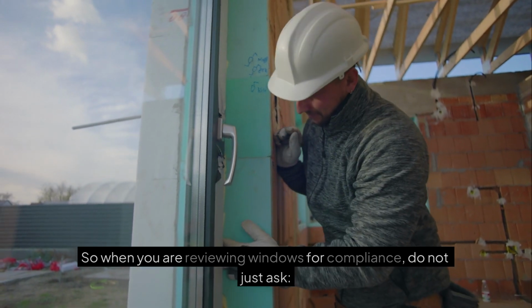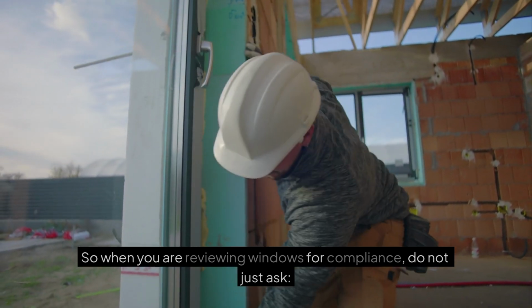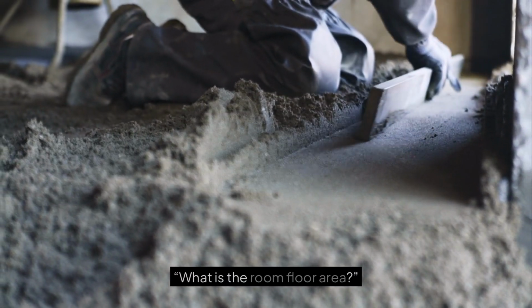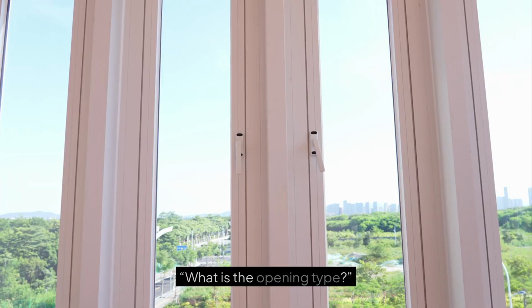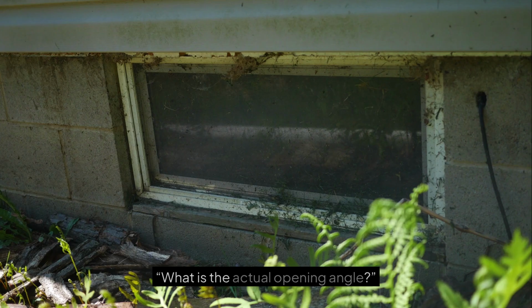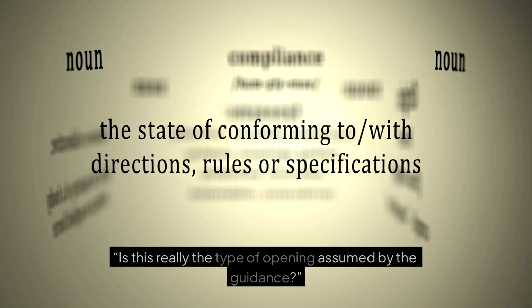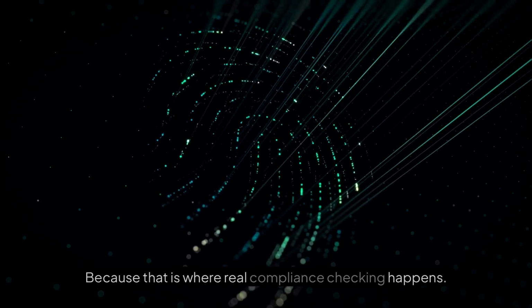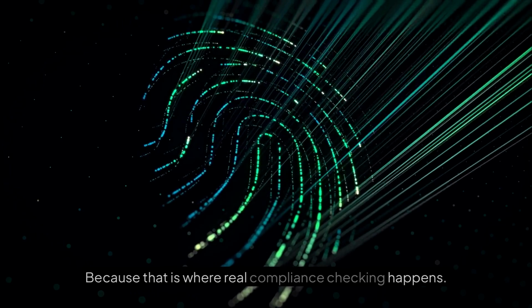So when you are reviewing windows for compliance, do not just ask, what is the room floor area? Also ask, what is the opening type? What is the actual opening angle? Is this really the type of opening assumed by the guidance? Because that is where real compliance checking happens.